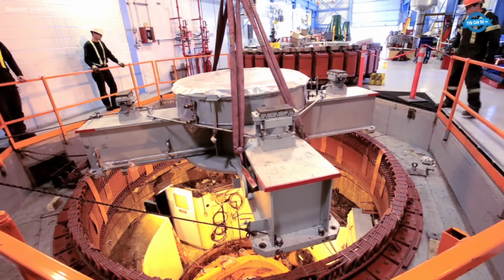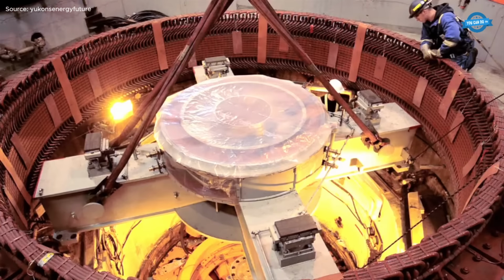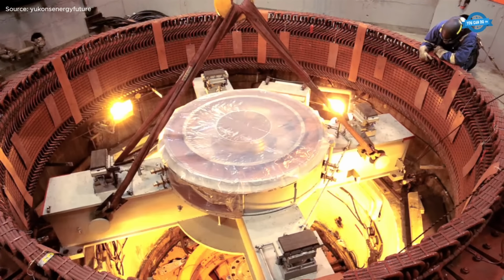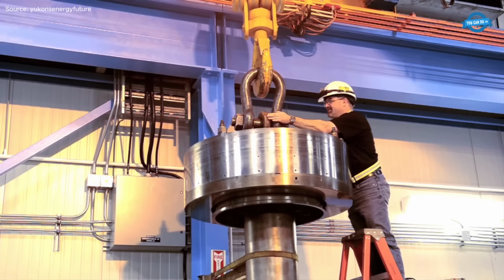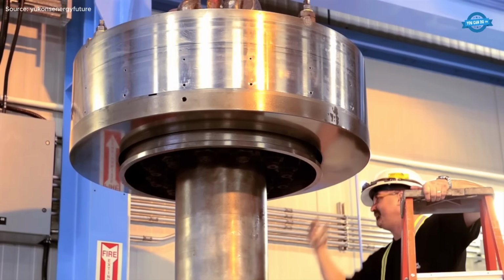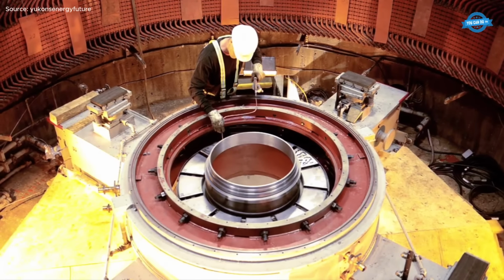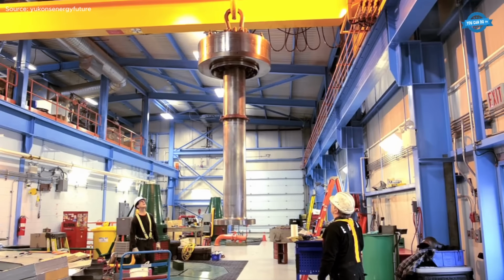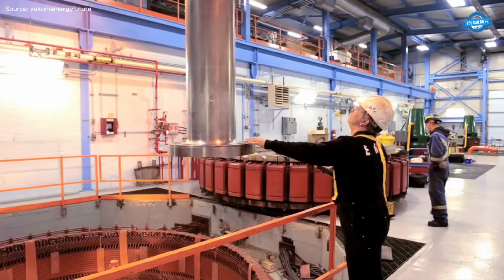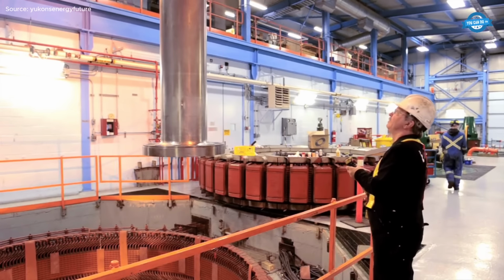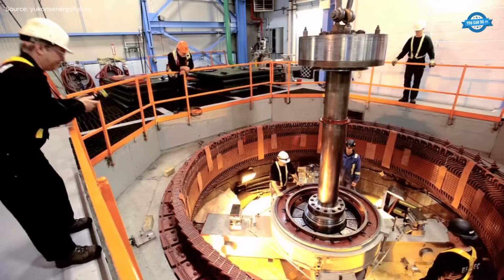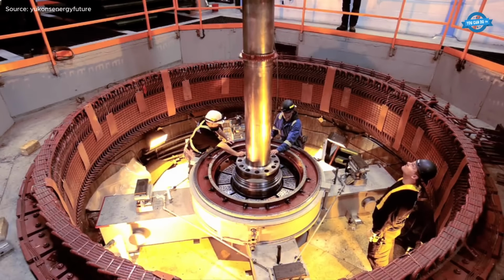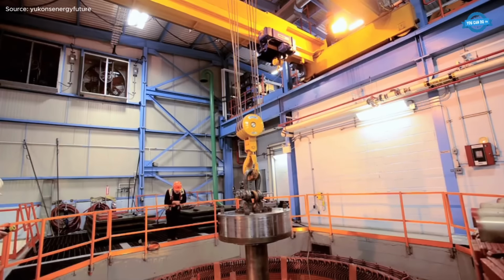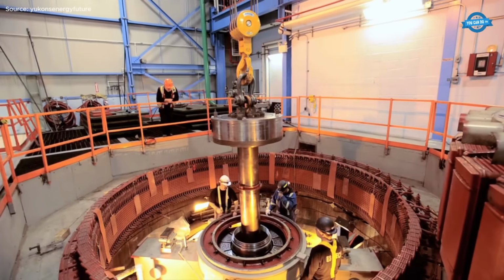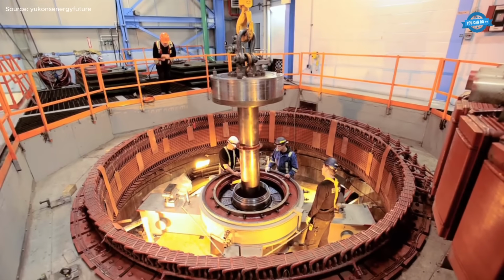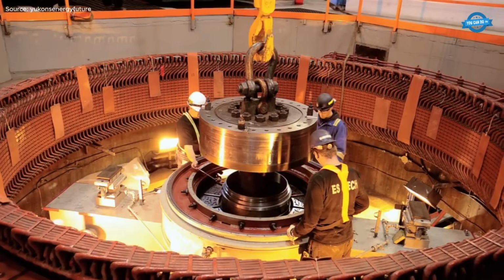What does it take to return a decade-old hydrogenerator to peak performance in the demanding climate of the Yukon? A 10-year overhaul of a Whitehorse hydrogenerator is a comprehensive engineering operation that restores reliability, efficiency, and structural integrity. The process begins with a controlled shutdown, followed by complete disassembly of the turbine generator unit. The rotor is lifted using heavy-capacity overhead cranes, while the stator, bearings, and excitation systems undergo detailed inspection. Dimensional checks, non-destructive testing, and insulation resistance measurements identify wear, thermal degradation, and mechanical fatigue.